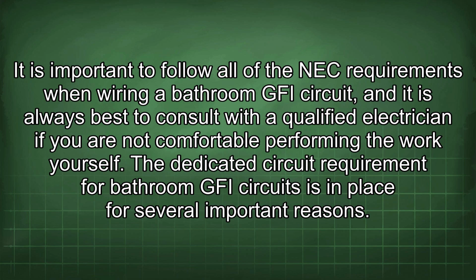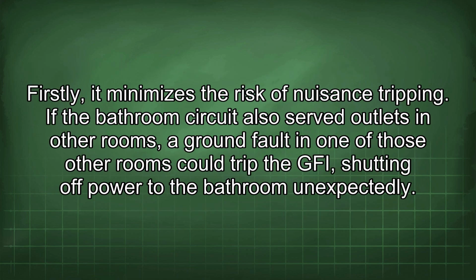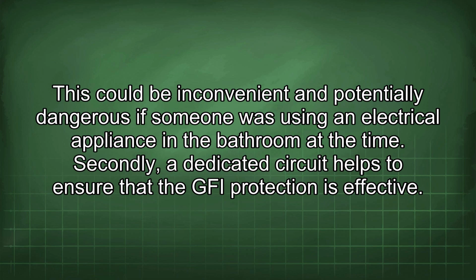The dedicated circuit requirement for bathroom GFI circuits is in place for several important reasons. Firstly, it minimizes the risk of nuisance tripping. If the bathroom circuit also served outlets in other rooms, a ground fault in one of those other rooms could trip the GFI, shutting off power to the bathroom unexpectedly. This could be inconvenient and potentially dangerous if someone was using an electrical appliance in the bathroom at the time.